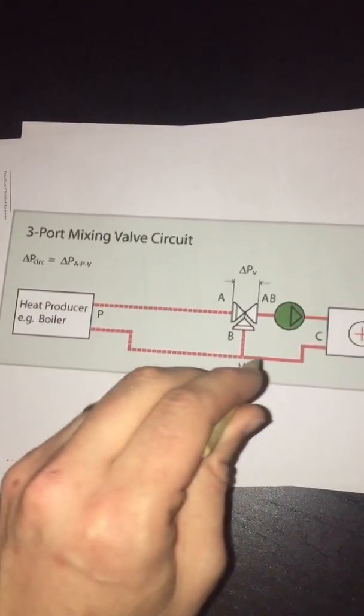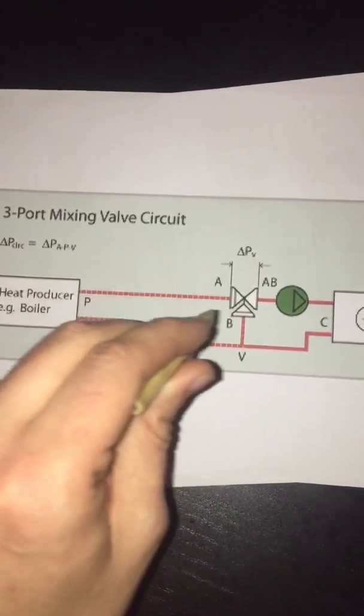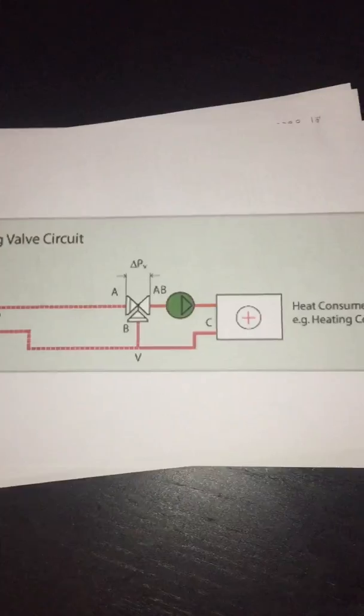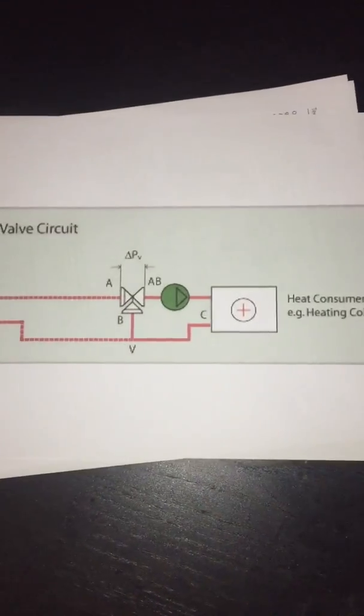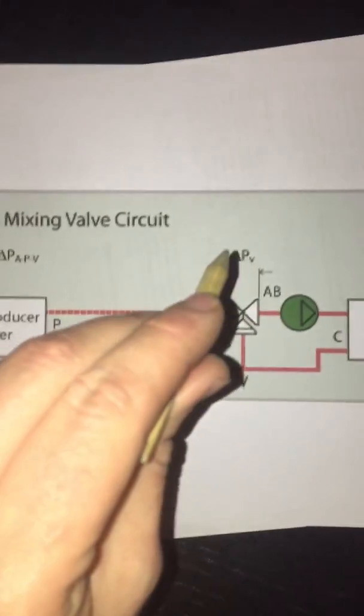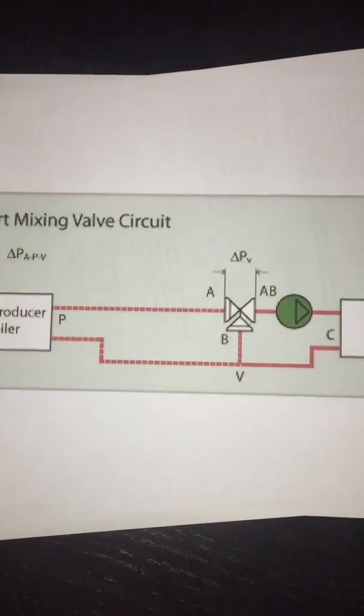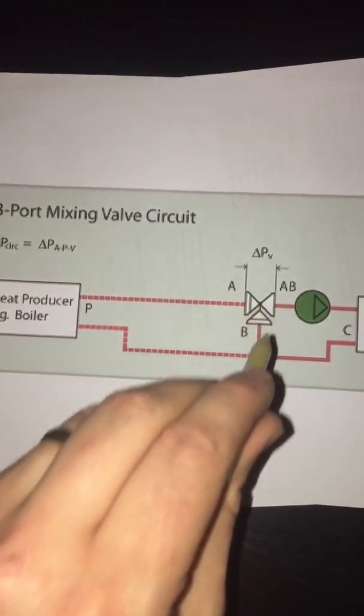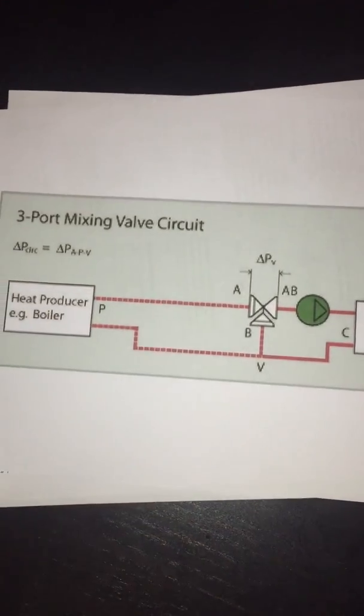So we have our flow from our boiler and our return from the boiler. It's blending down to give reduced flow temperature, say, to often an underfloor heating circuit here. So the delta P across this valve wants to be between 20 and 50% roughly of the delta P across the entire circuit including the valve.